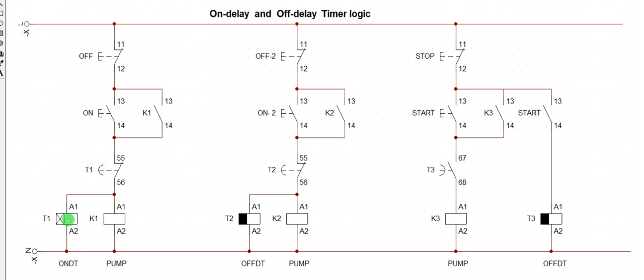You now see that I feed my timer through the contact of the timer. I repeat, I feed the timer through the contact of the timer because I want the entire system to shut down. If I want the timer to maintain power while shutting down this, I will change the logic. I will feed this timer from another means, not coming from here. Because I want the logic to shut down, that is why I feed the timer through the contact.